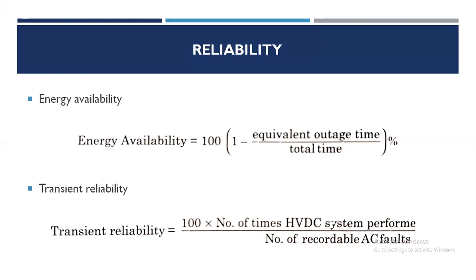The energy availability or transient reliability of existing DC systems with thyristor valves is 90%, 95% or more. The average failure rate of thyristors in a valve is less than 0.6% per operating year. It is common practice to provide redundant thyristors in the series string composing a HVDC valve so that failed thyristors can be replaced during the scheduled maintenance period. The maintenance of thyristor valve is also much simpler than the earlier mercury arc valves. Some of the HVDC outage statistics is given in this table.